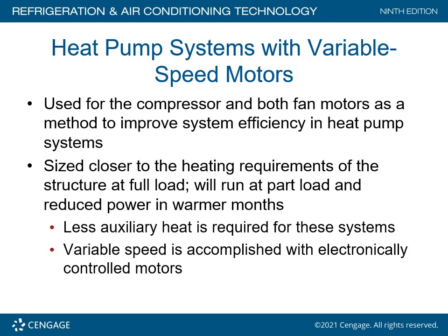Heat pump systems with variable speed motors utilize them for the compressor and both fan motors as a method to improve the system efficiency in the heat pump system. They're sized closer to the heating requirements of the structure at full load and will run at partial load and reduce power in the warmer months. Less auxiliary heat is required for these types of systems. Variable speed is accomplished through an electronically commutated motor, ECM, or the constant torque motor design.